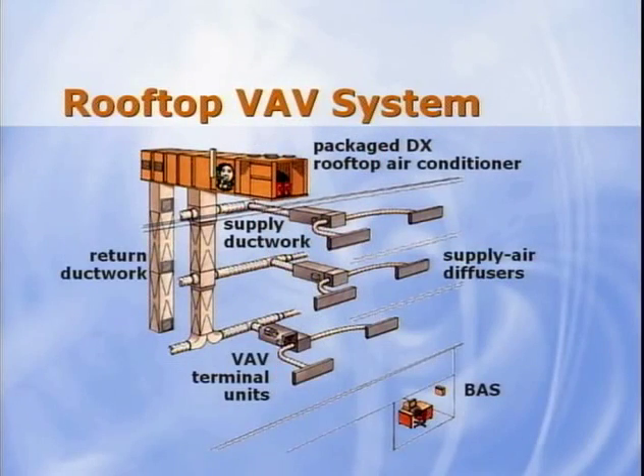Now, let me take a few minutes to frame a typical rooftop VAV system. Then Phil, John, and Paul will cover concepts to reduce energy use. A rooftop VAV system consists of a packaged rooftop air conditioner that can serve either a single zone or multiple individually controlled zones. In multiple zone systems, each zone has a VAV terminal unit controlled by a temperature sensor in that zone. A building automation system helps all the pieces talk to one another.